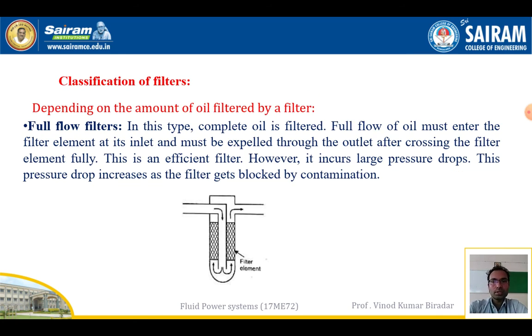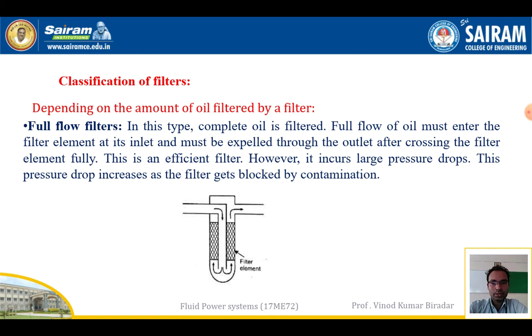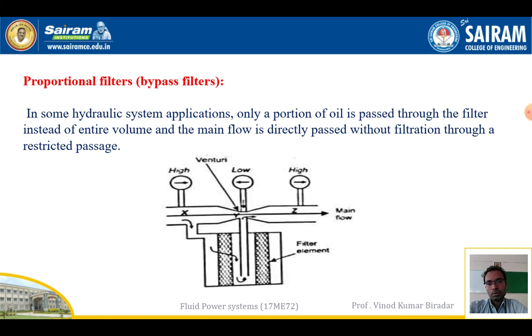Filters are classified based on the amount of oil filtered. The first type is the full flow filter. In this type, the complete oil flow must enter the filter element at its inlet and be expelled through the outlet after fully crossing the filter element. This is an efficient filter; however, it causes large pressure drops, which increase as the filter becomes blocked by contamination.